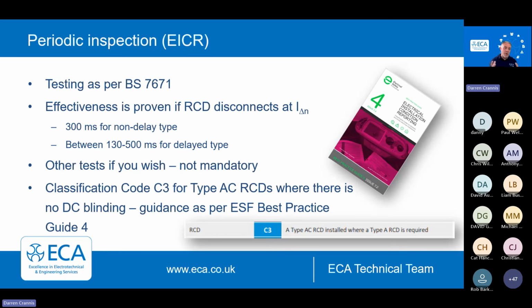Again, that carries forward when we're periodic inspecting. So again, Best Practice Guide 4 from Electrical Safety First is an excellent guide when you're doing EICRs. Again, we're just asking for that I delta n. Other tests aren't mandatory, but may help you if you're fault finding. For example, I know a lot of people favour the ramp test if you're seeing something that looks a bit sensitive. Classification codes for these typically, and again, this is a starting point, it's you as the inspector on site that makes the final decision.